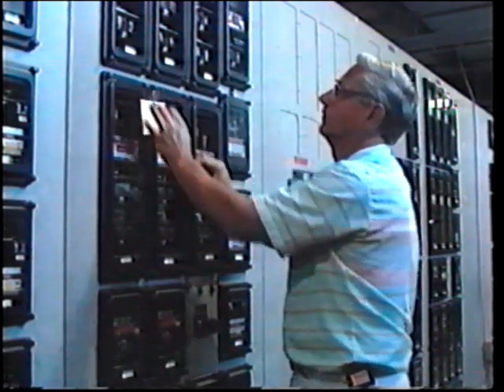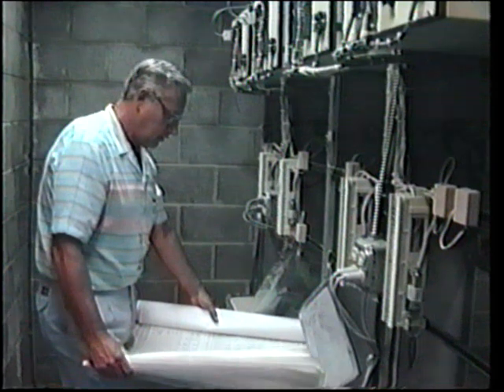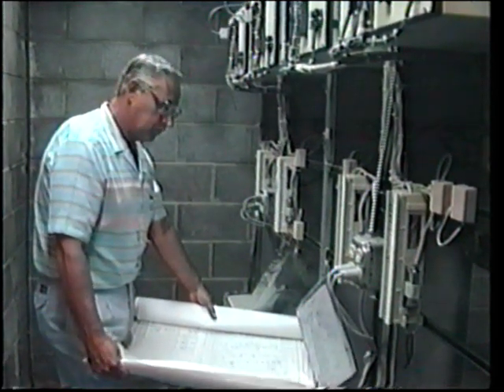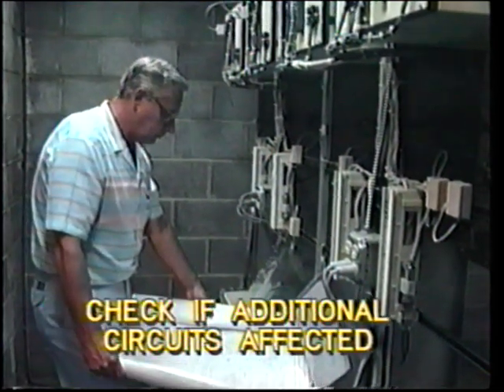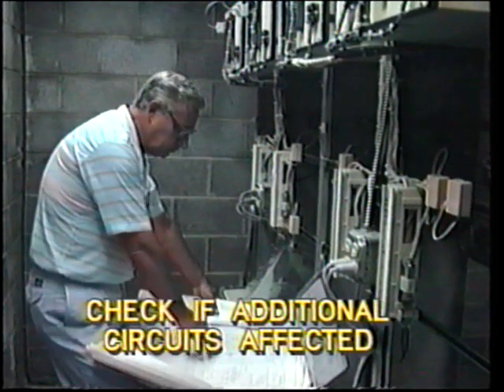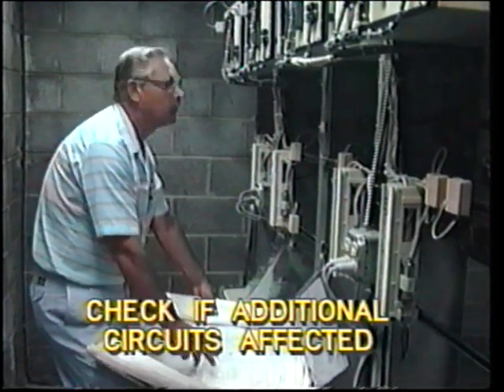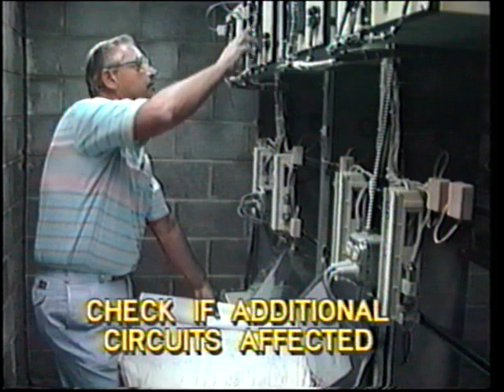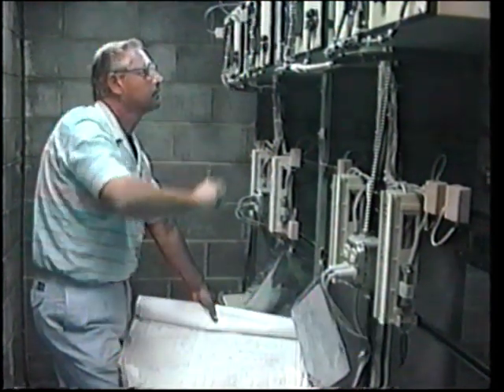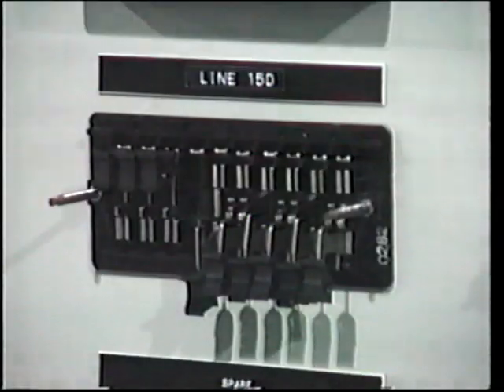Perhaps your company does this the other way around. When you are taking in-service load readings, be careful to check if any additional circuits may be affected. For example, an unbalanced phase relay may possibly cause an associated ground relay to operate. Before commencing work, take note of the as-found position of all test switches. On completion of your work, they must be returned to the original position.